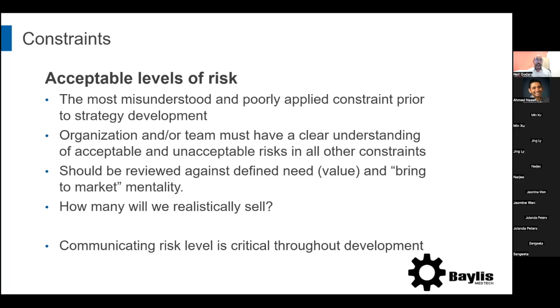The amount of testing we do on products that is above and beyond the requirement is probably two-thirds of it, and one-third is the requirements. And what do we use that two-thirds of testing for? We use it to determine how close to the sun we are, how close we are to not only the technical and regulatory requirements, but the business requirements of product performance or manufacturing yield or other things. We really want to understand exactly what we've made, so that we know what risks we're taking on. And if we're comfortable with the risks, then we'll go forward.